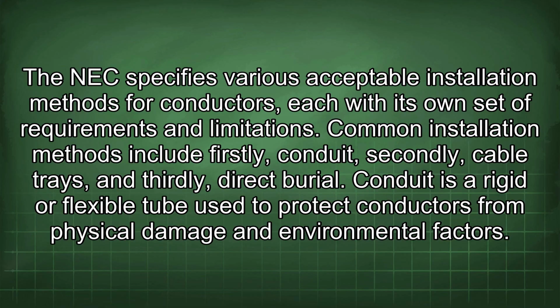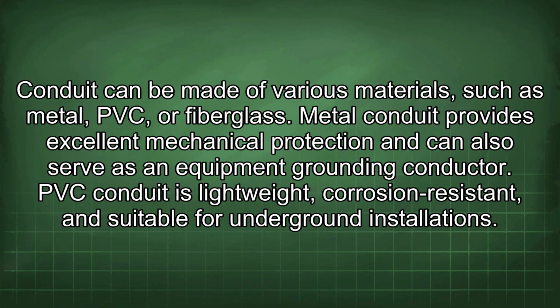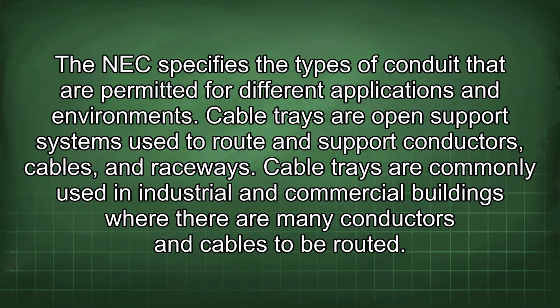Conduit is a rigid or flexible tube used to protect conductors from physical damage and environmental factors. Conduit can be made of various materials, such as metal, PVC, or fiberglass. Metal conduit provides excellent mechanical protection and can also serve as an equipment grounding conductor. PVC conduit is lightweight, corrosion resistant, and suitable for underground installations. The NEC specifies the types of conduit that are permitted for different applications and environments.